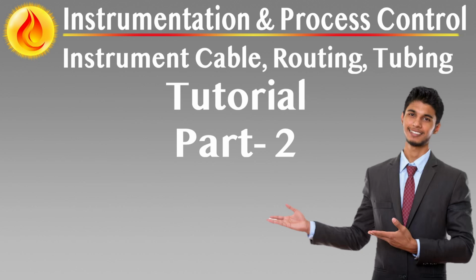Where copper-based communication is used, galvanic isolation must be employed at both ends of the circuit to minimize the propagation of induced voltages and to protect sensitive electronic interfaces. Shield continuity and correct earthing practices remain critical to maintaining system integrity under surge conditions.